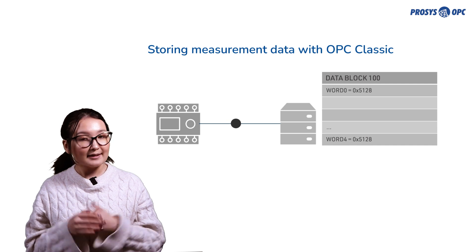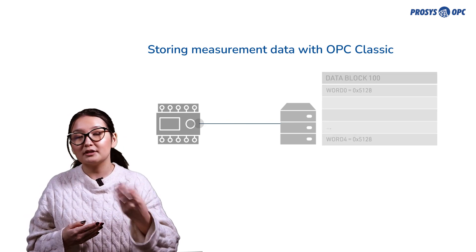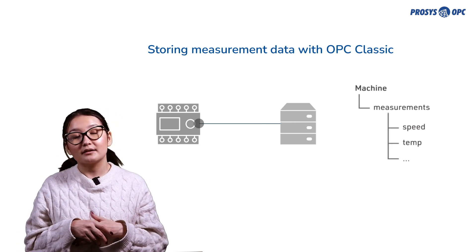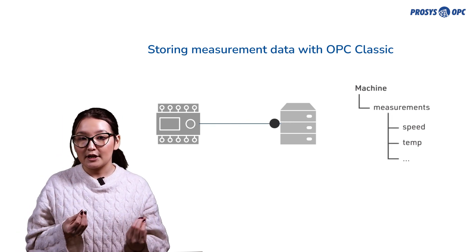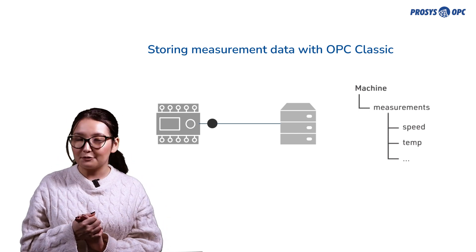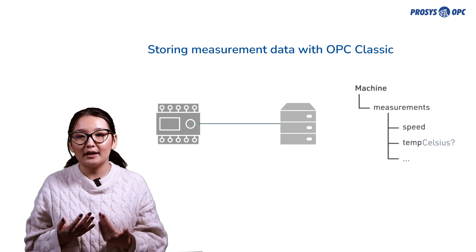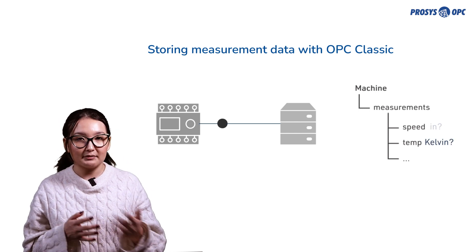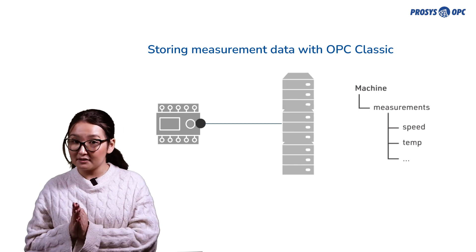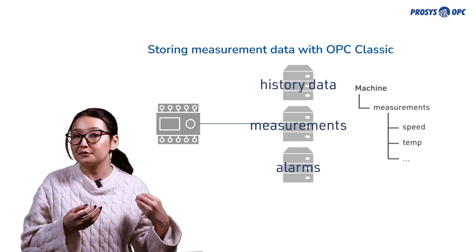In OPC Classic, a significant step forward was the introduction of human-readable names for measurements. The next step was the hierarchical layout of the address space, which made it way easier to browse through the data of an OPC Server. However, OPC Classic could not really show any other relationships between the measurements and the parameters. Also, alarms and history data were separated from the current measurements on their own servers.